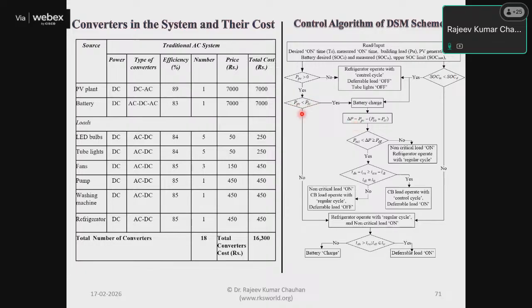The system calculates building load versus PV generation. If the power generated by the PV panel is less than the building load, and the measured state of charge is less than desired, it will ask the battery to charge first. If this is not the situation, it will keep the battery either isolated or discharge it to supply the load.